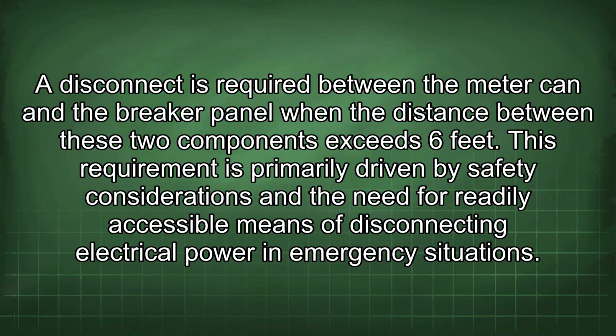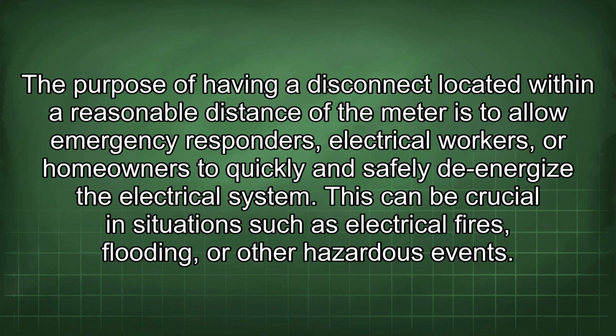A disconnect is required between the meter can and the breaker panel when the distance between these two components exceeds 6 feet. This requirement is primarily driven by safety considerations and the need for readily accessible means of disconnecting electrical power in emergency situations. The purpose of having a disconnect located within a reasonable distance of the meter is to allow emergency responders, electrical workers, or homeowners to quickly and safely de-energize the electrical system. This can be crucial in situations such as electrical fires, flooding, or other hazardous events.